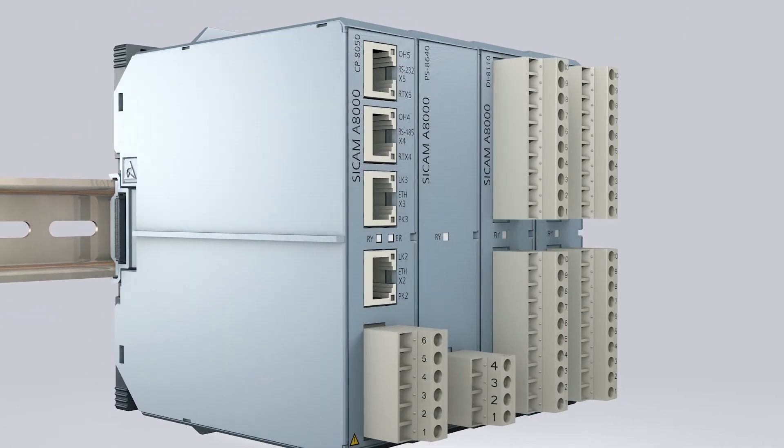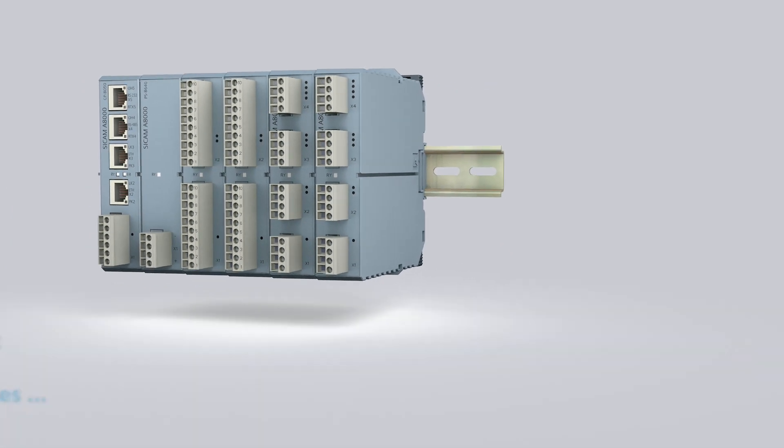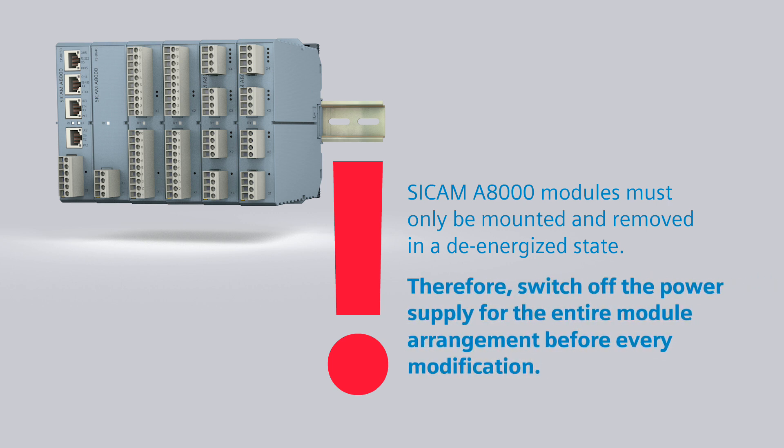Mount all other modules in the same way. Please note: SICAM A8000 modules must only be mounted and removed in a de-energized state. Therefore, switch off the power supply for the entire module arrangement before every modification.